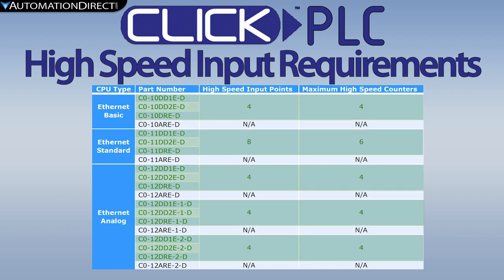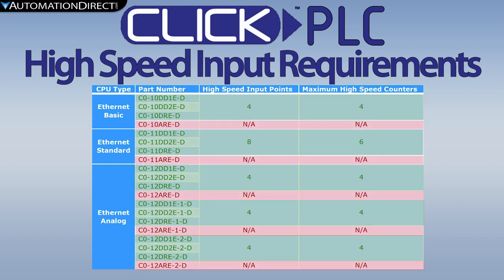To use high speed inputs on Click, you must have a Click CPU that supports Ethernet and has DC inputs. High speed counting is not supported on units with AC inputs.